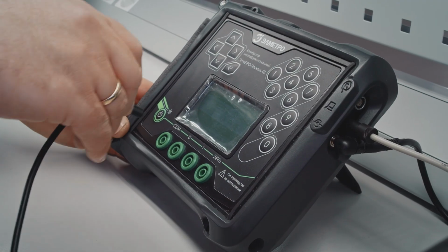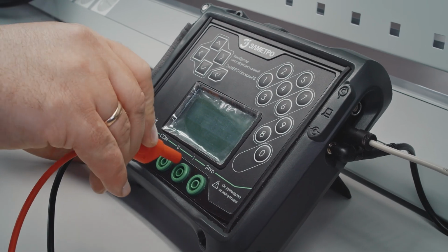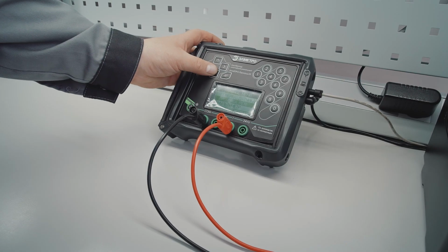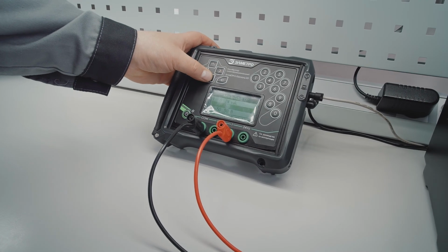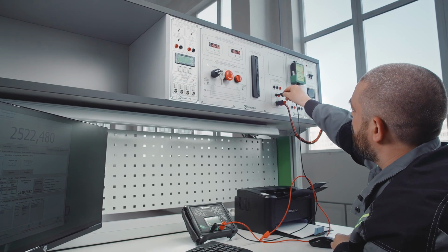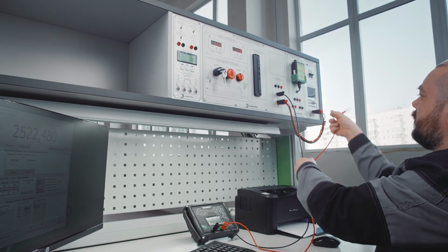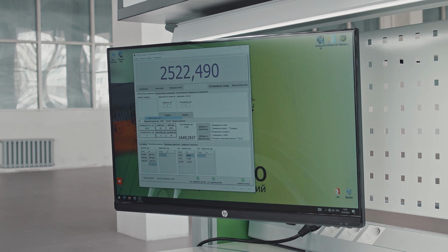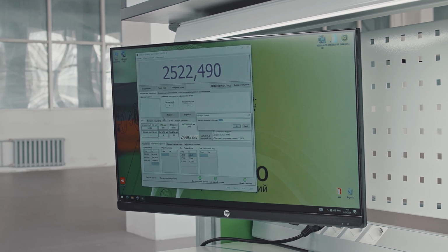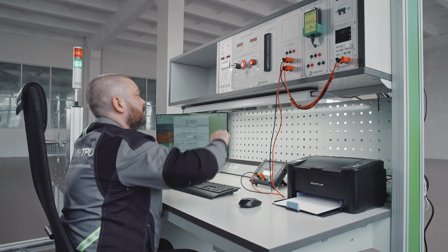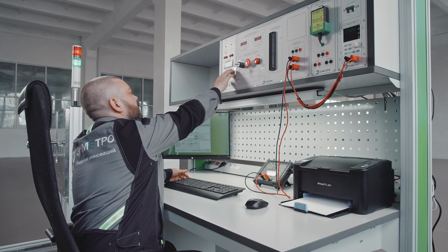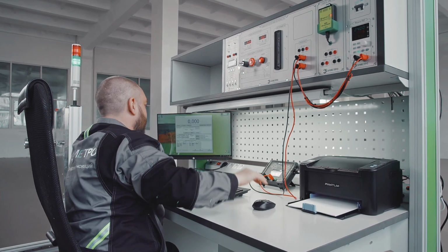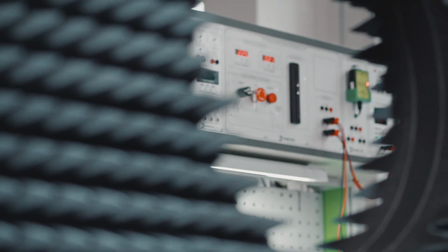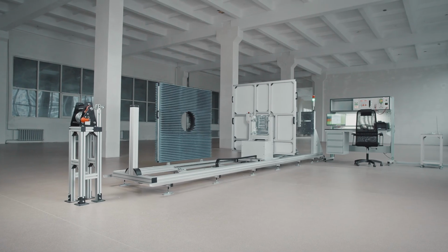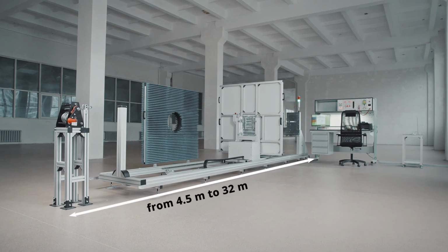One of the main functional elements of the bench is ELMETRO Pascal 03 standard calibrator of amperage and voltage. It receives the readings from the level instrument. It is supplied with the ARM Eurovan software that allows for maximum automation of the level instrument's verification and enhances the operator experience when working with the bench. The bench dimensions vary depending on the requirements of the client and range between 4.5 and 32 meters.